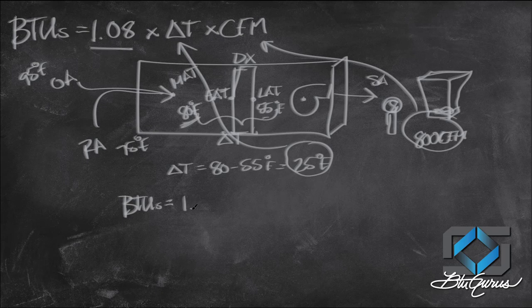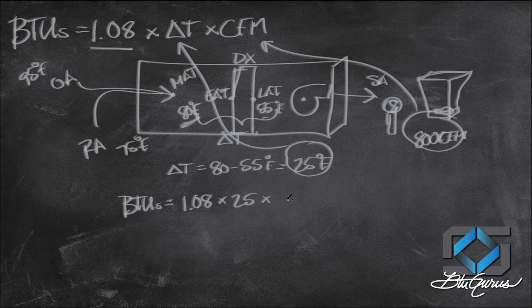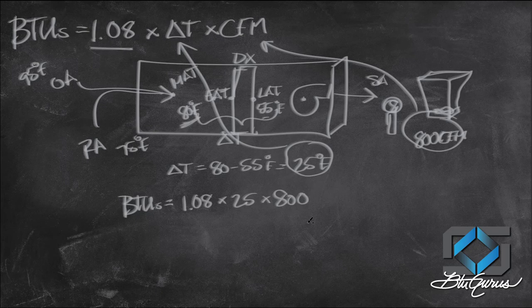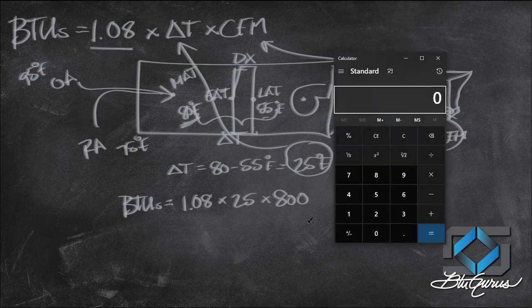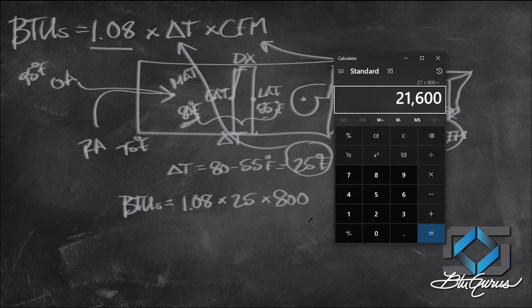It equals 1.08 multiply that by 25 degrees delta T, and I multiply that by 800 CFM. To follow along with that, let me open up my calculator. 1.08 times 25 times 800.